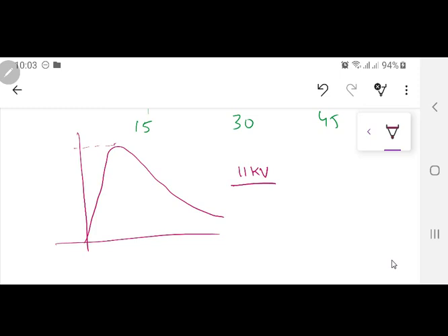And on the secondary side there is a load connected also which is going to turn on, and since the transformer also has an inductance, it will take a huge amount of current, and the time of the switching is such that L di/dt becomes very large. An 11 kV transformer can experience a 65 kV peak impulse also. This is switching, but in some cases there can be a lightning strike also.